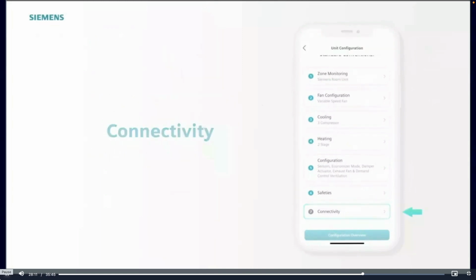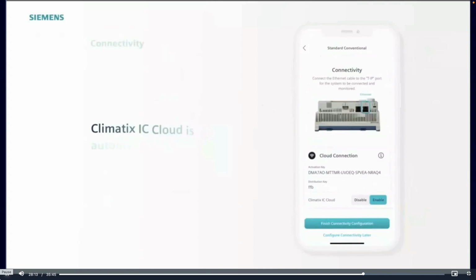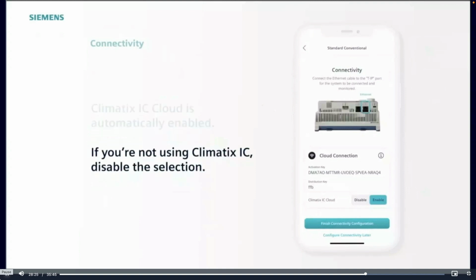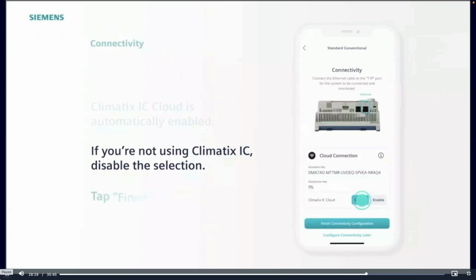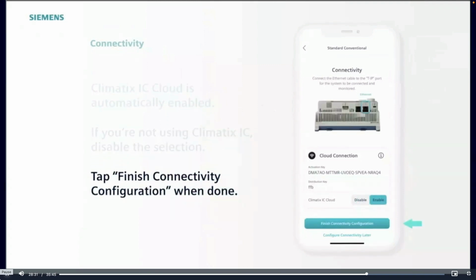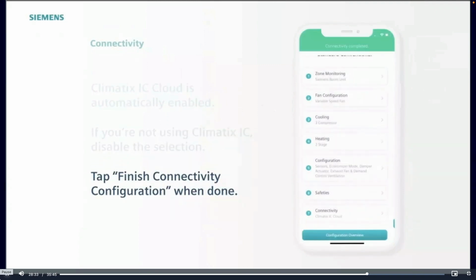The final step is connectivity. Climatix IC Cloud connectivity is automatically enabled. The activation key will be automatically read from the controller, and the distribution key is specific to the distributor or contractor who is installing the equipment. If you're not using Climatix IC, you just disable the selection and the controller will not connect. If it looks good, tap Finish Connectivity Configuration.